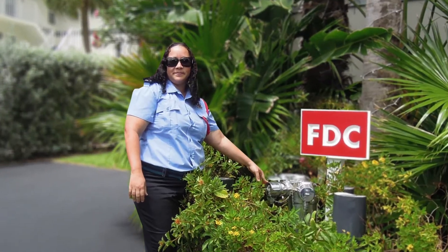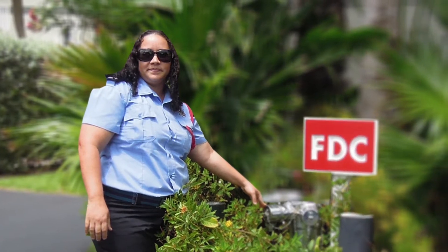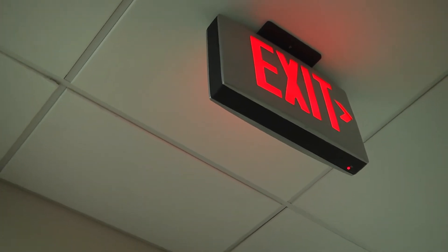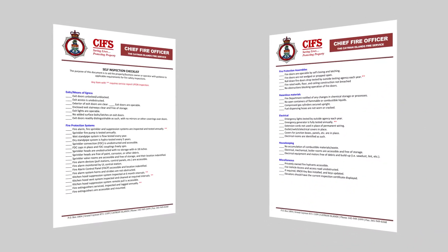A few things to remember when I arrive at your property for inspection. You need to provide your annual service reports, your fire alarm service report, and your fire pump service report if you have a fire pump on property. Remember, exit signs should be illuminated at all times and a log kept for 30-day interval checks throughout. Your elevators should be annually serviced and tagged by the planning department. In order to do so, you need to book an inspection with the planning department to have your elevator recertified.